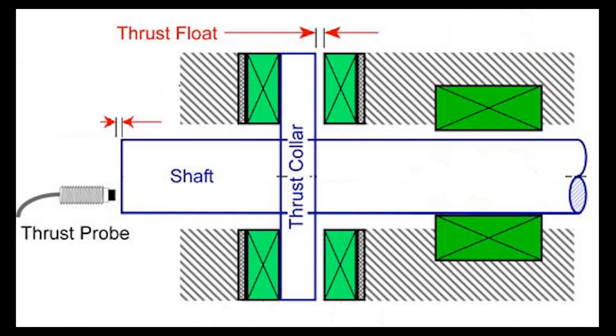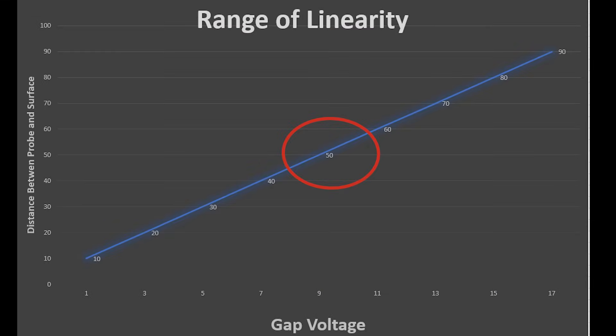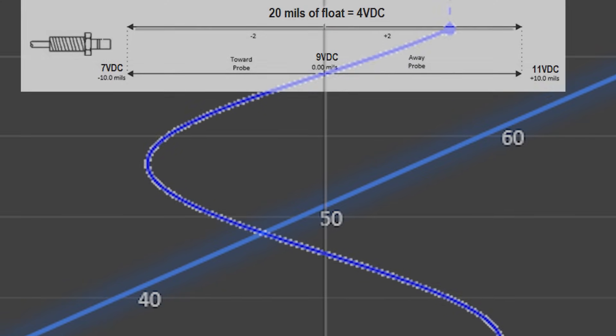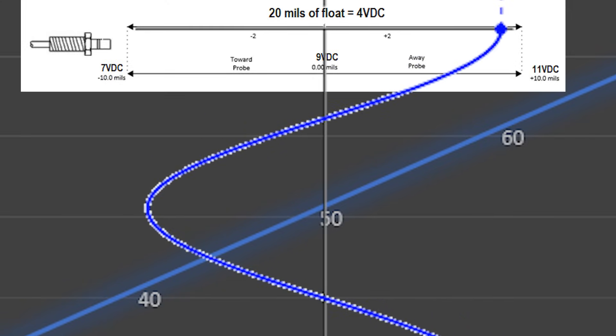The axial float of a rotating shaft can be measured using this gap voltage. When used in this type of application, the probe is mounted facing the end of the shaft. The initial gap voltage setting is established to align the center of the linear range with the center of the total shaft float. Any axial displacement will create a change in voltage.